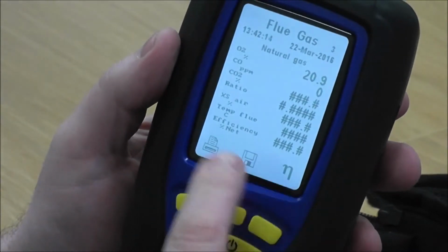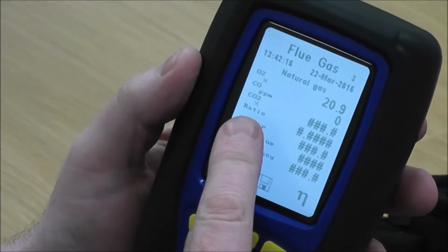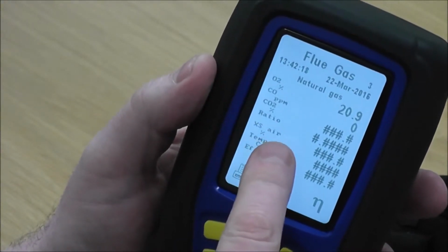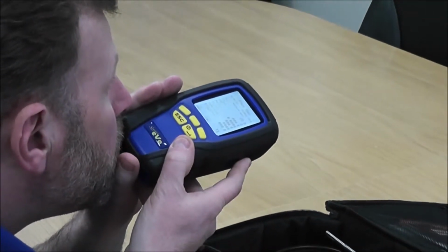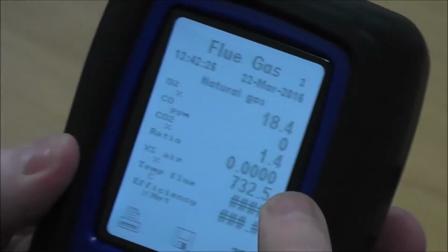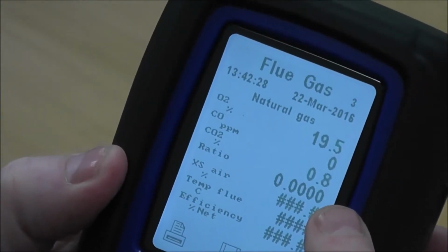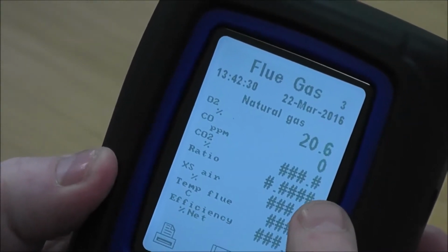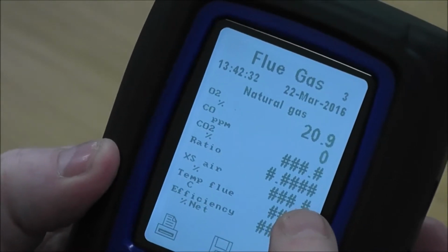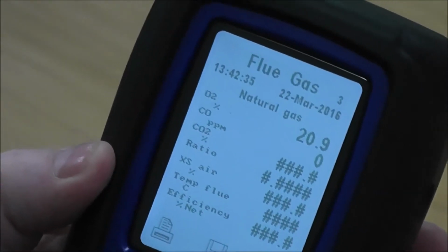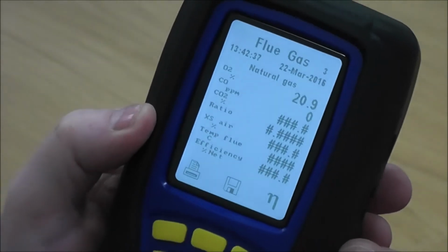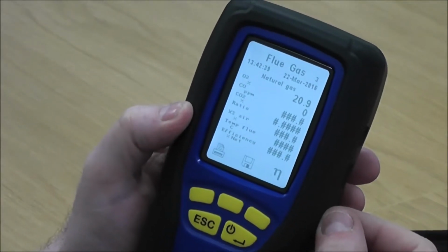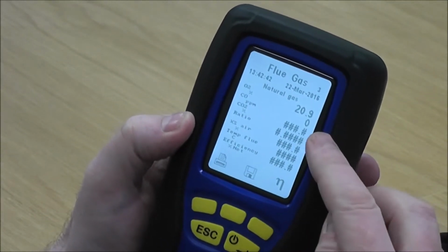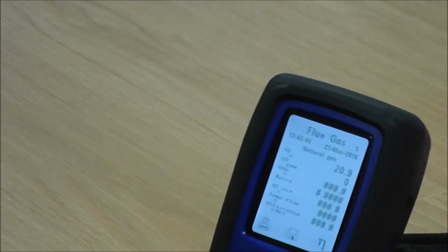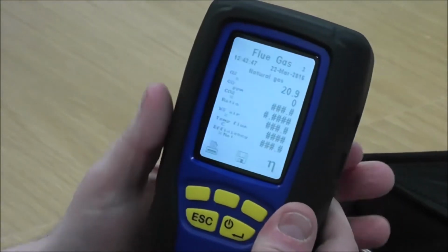Now if I do this again, this time I would like you to concentrate on the third and the fourth line down, the CO2 and the ratio. So if I blow on that again, and we quickly look at those lines, you'll see the CO2 just cuts in, just enough that it calculates and shows you a CO2 reading, your ratio periodically cuts in as well. That just tells you that your oxygen is calculating your CO2, and again it's all returned back to 20.9 in a timely fashion, which means it's very responsive, and it doesn't look like we've got too many problems with this analyzer.